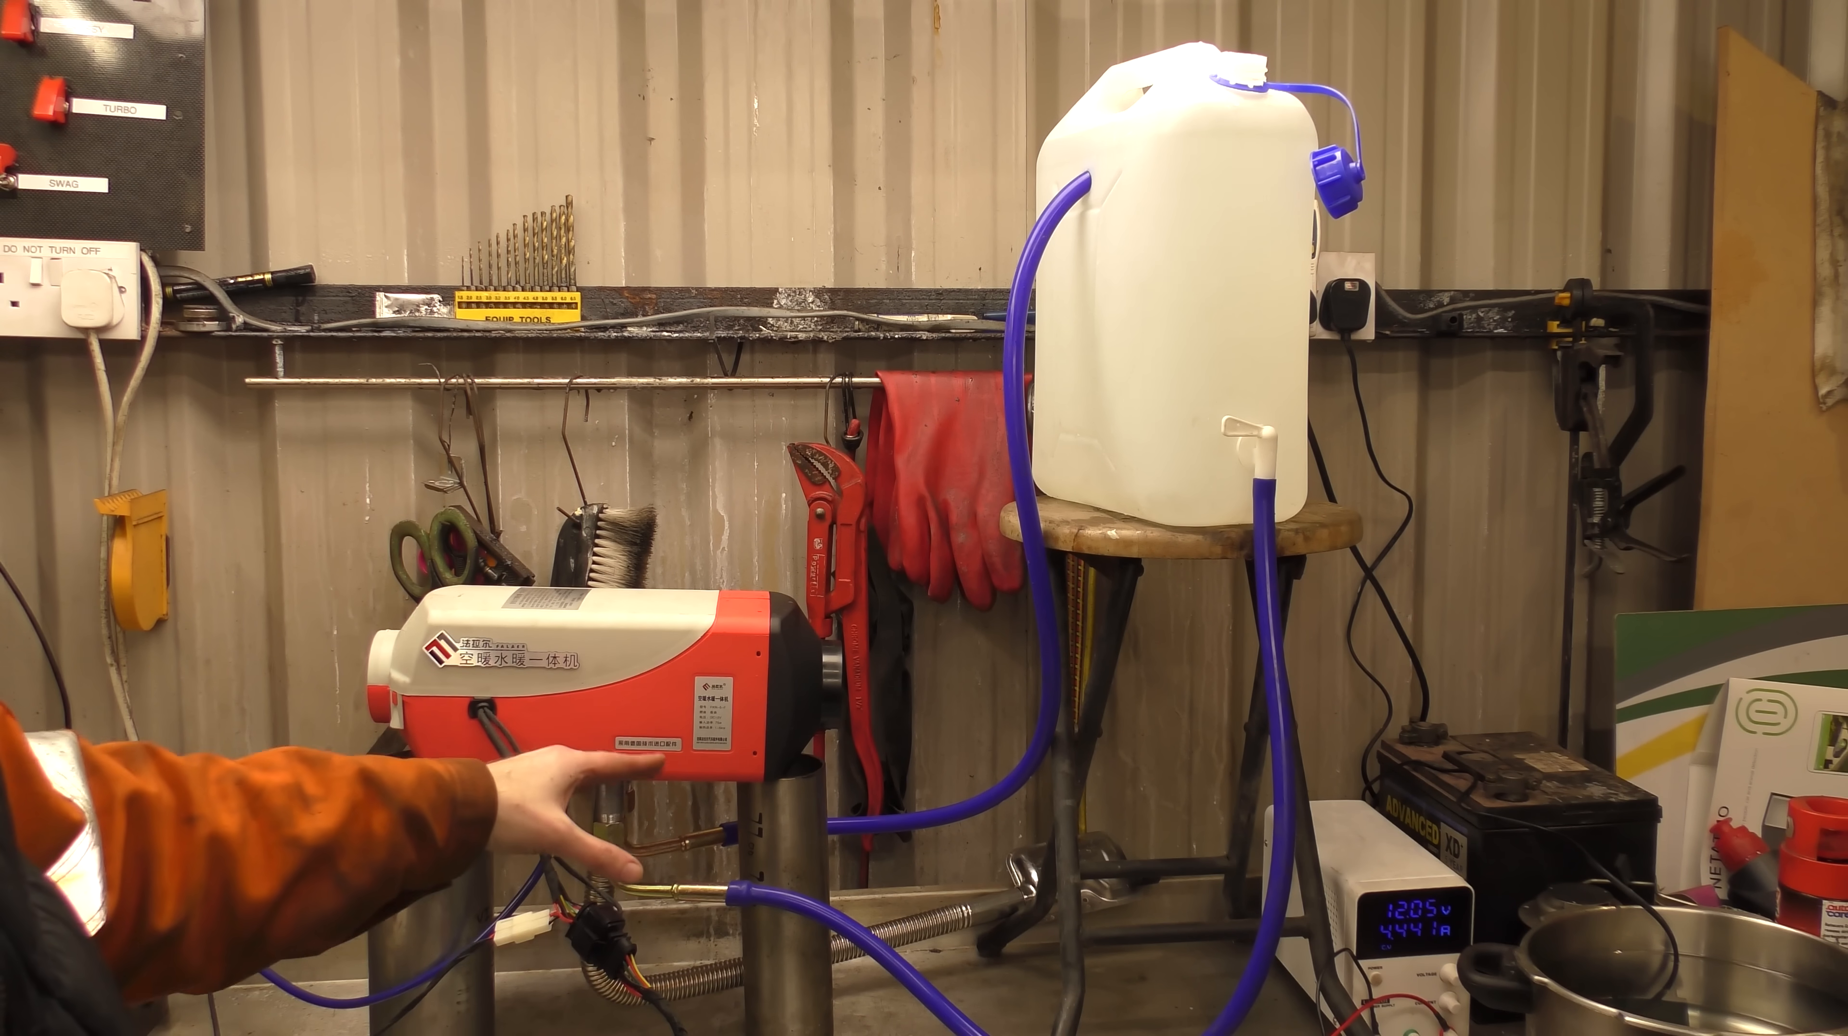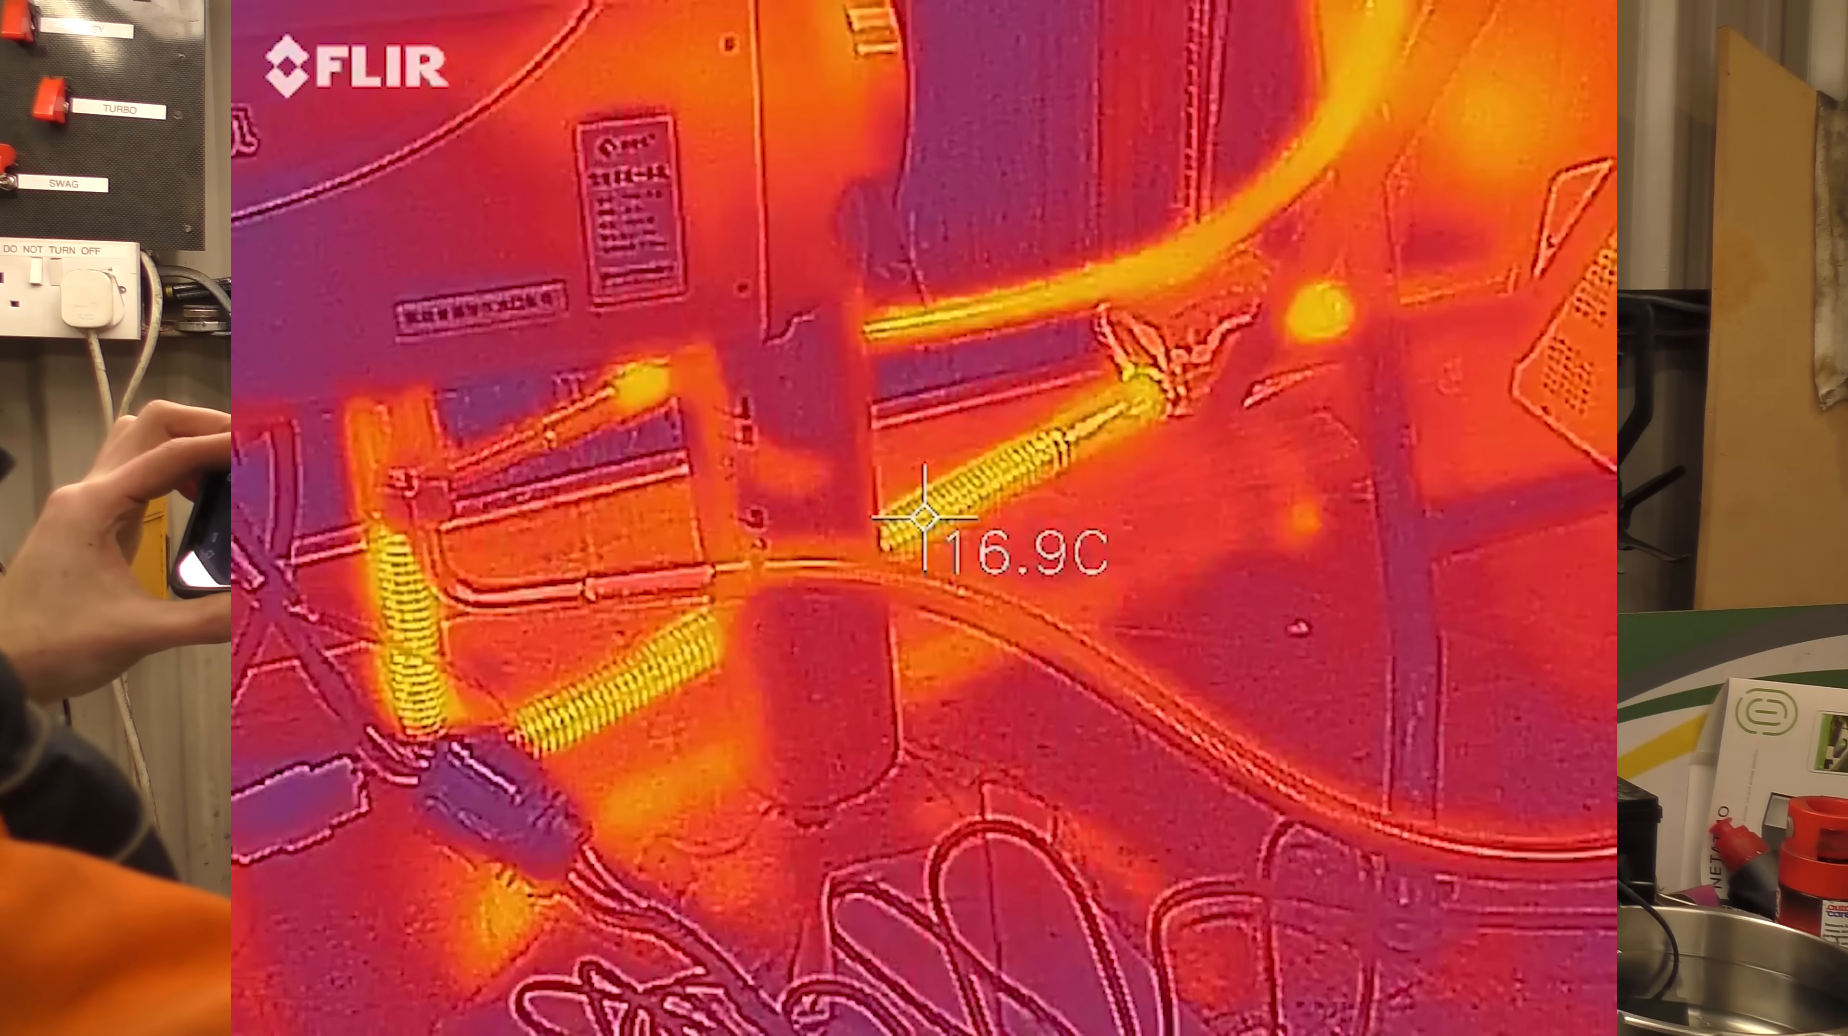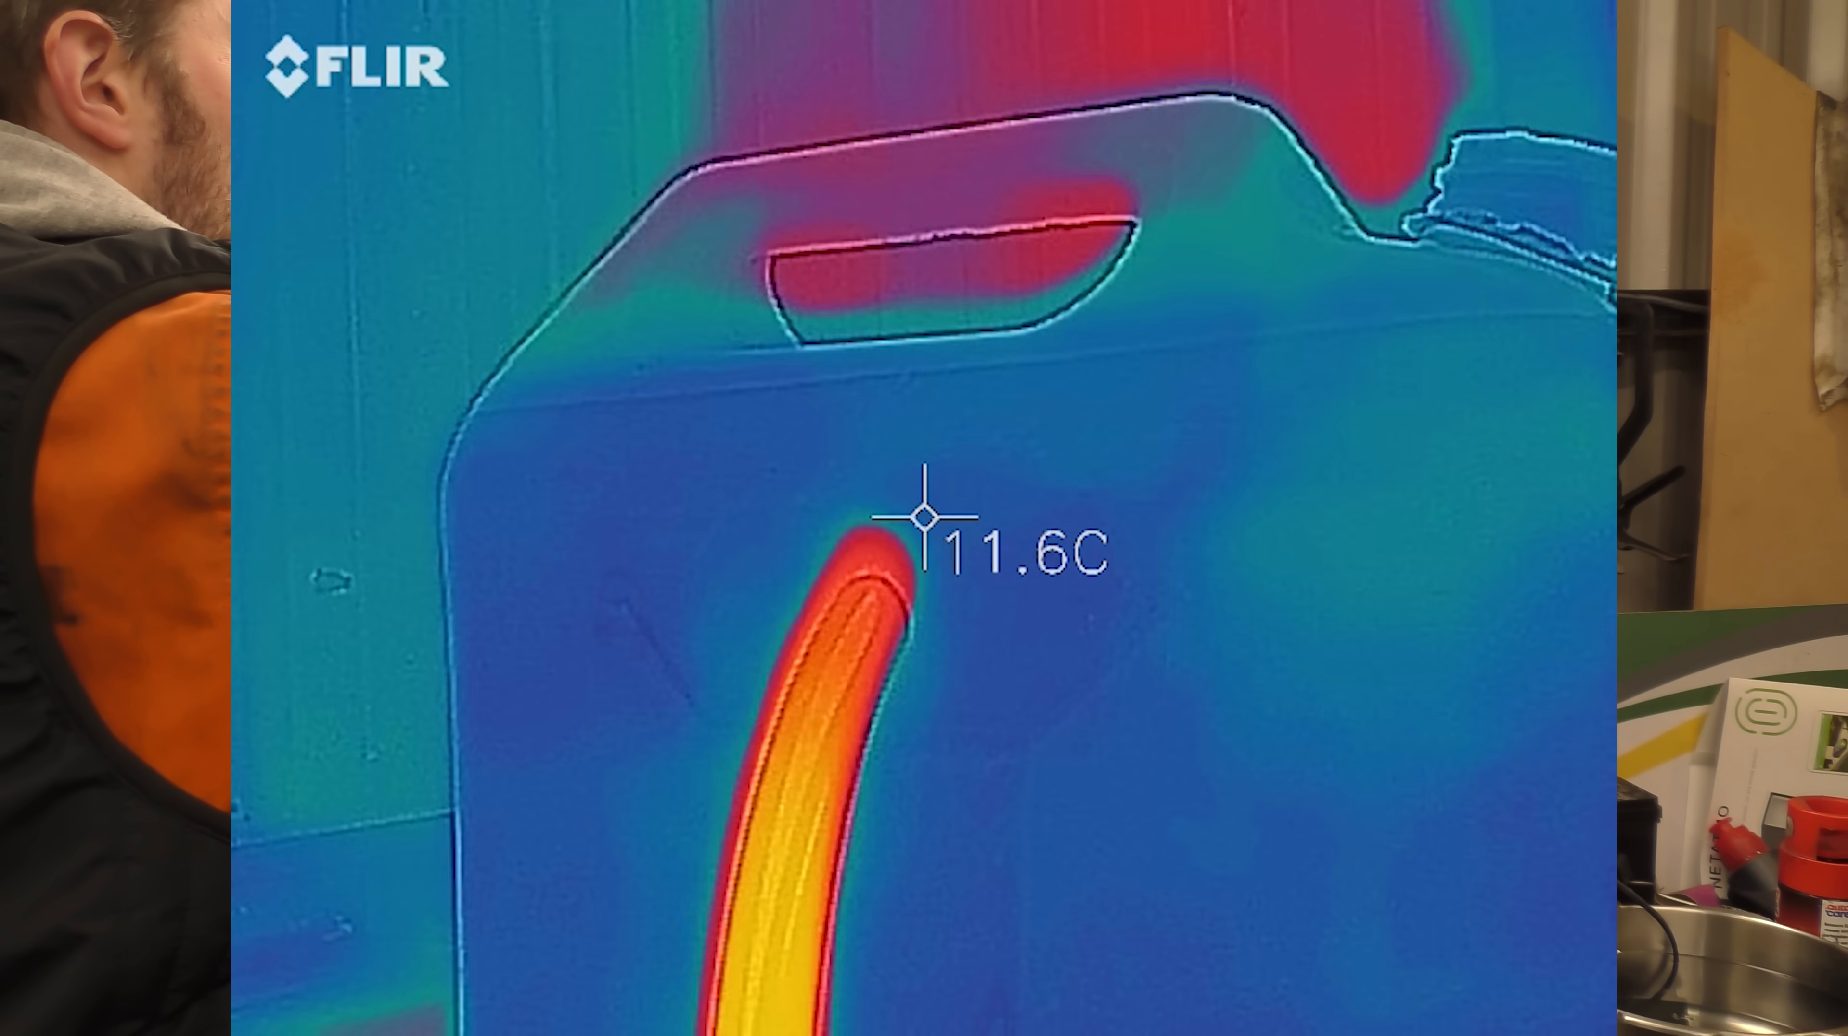There's obviously not enough flow through here. So what we're just getting is one pipe slightly warmer than the other, and we're not really getting thermosyphon action. It's just glugging and spitting out boiling water every now and again, which isn't what you want.